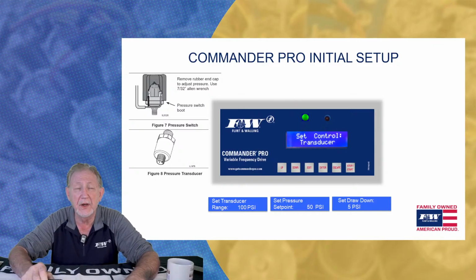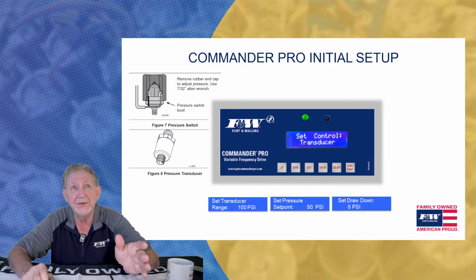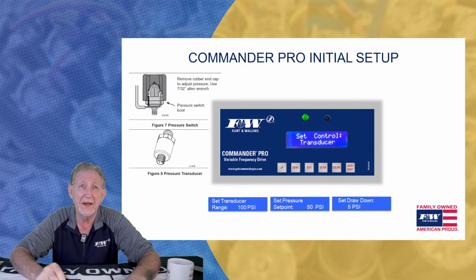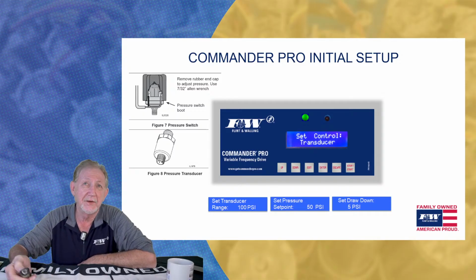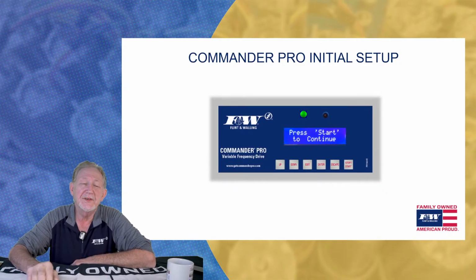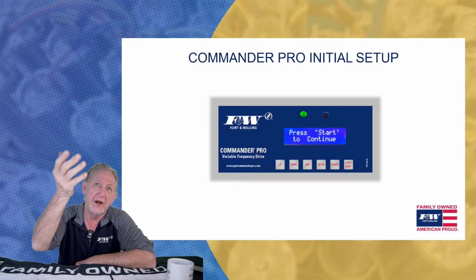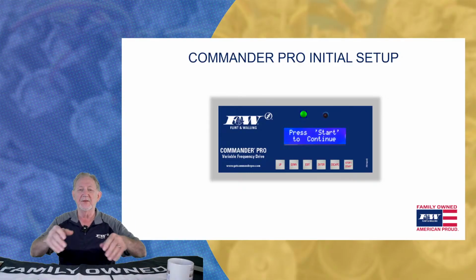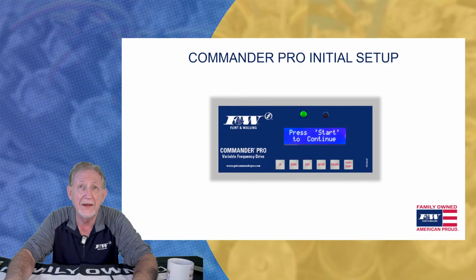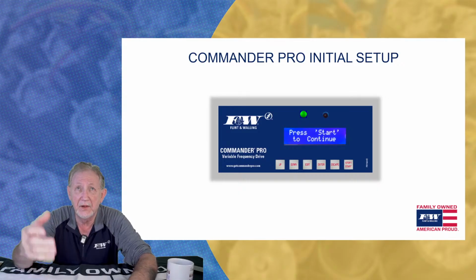You probably have to look at a pressure gauge to watch where you're going with that. But nonetheless, that's how you would set the pressure set point on a switch, which is why a lot of guys like the transducer, because it seems to be something a little easier to set. All right, so once you've done that, that's the startup menu. It doesn't take too long to run through that, as long as you know what motor you've got, what the max amps are, and so on and so forth.